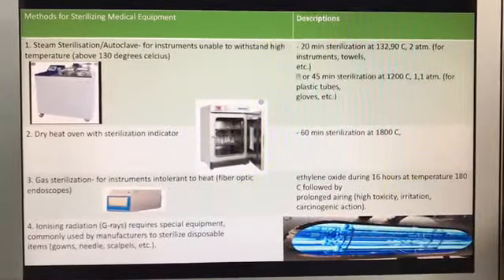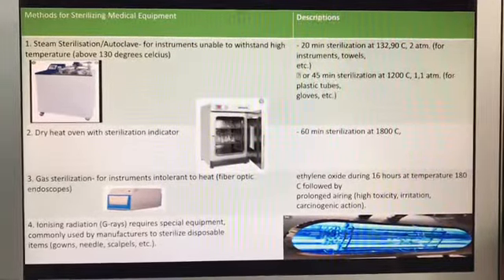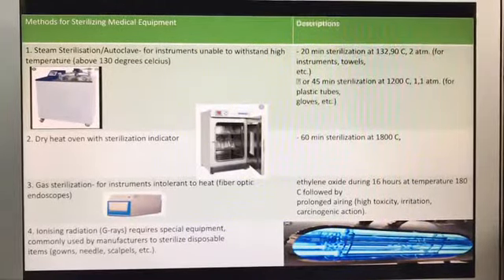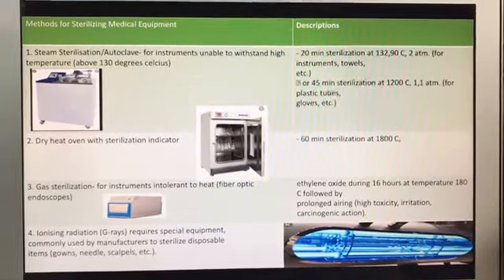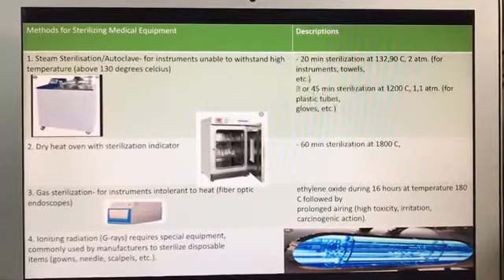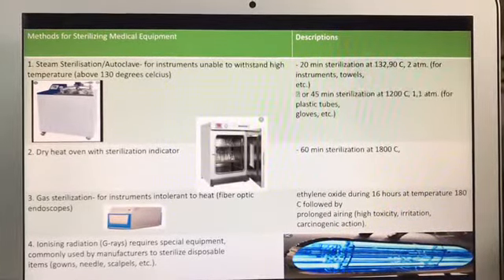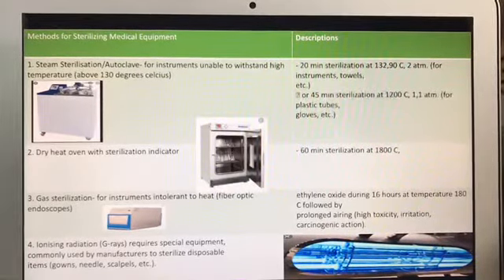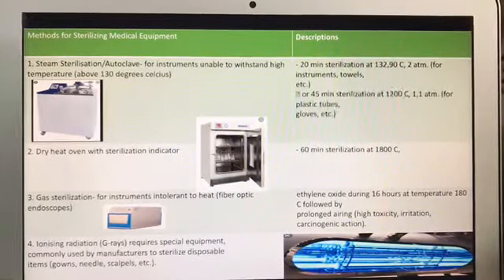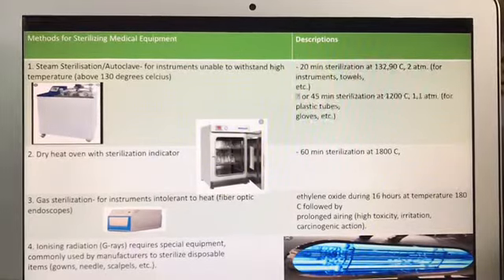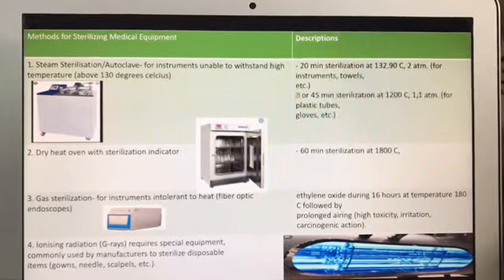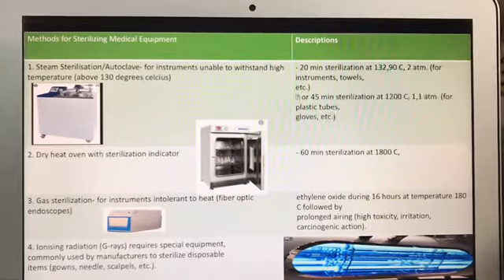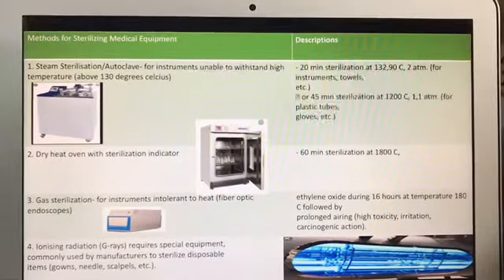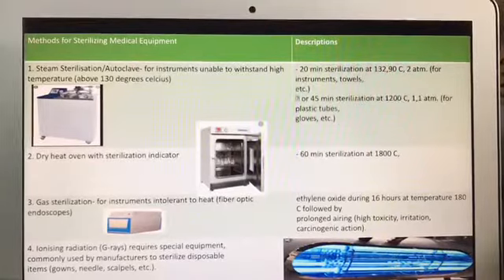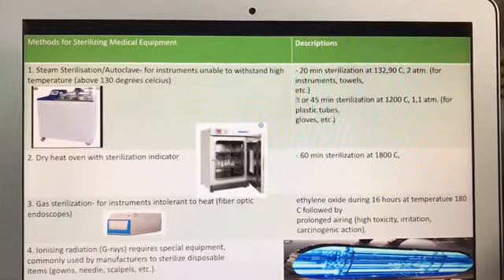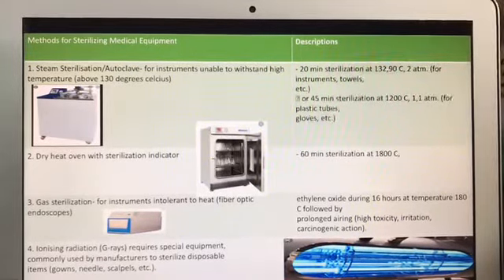Next, we have gas sterilization, which is for instruments intolerant to heat, for example fiber optic endoscopes. One example is plasma gas sterilizers. This type of sterilization uses low-temperature hydrogen peroxide-based gas plasma inside a chamber to kill any microorganisms on dental and medical equipment, including spores, bacteria, fungi, and viruses. When you add the vaporized hydrogen peroxide to the chamber, it sterilizes the enclosed equipment, and once you remove the vapor from the chamber, it produces a lower-temperature plasma which ensures total sterilization for all equipment. Oxygen and water are the remainder of this process, which makes these sterilizers safe for both the environment and medical staff. While this is a more costly method, it's extremely effective and an excellent option for medical equipment and tools that are moisture sensitive.